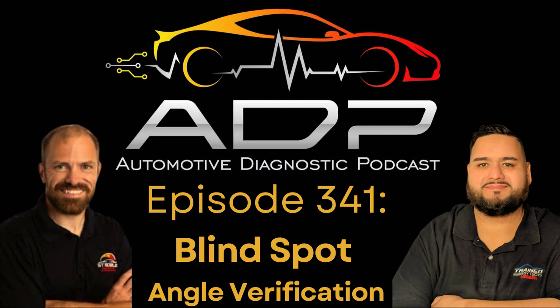Now, this is kind of getting into the meat of the episode and why I want to talk about this. There are two angles that you need to verify on these sensors before you do the actual calibration. All right, now there's a horizontal and a vertical, right? If you think of the horizon, that's side to side, and vertical is up and down. The vertical is easy, this is simple. If you have an angle gauge, you could use a bubble angle gauge. I have a digital one.